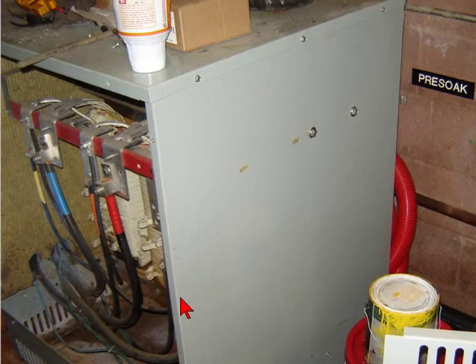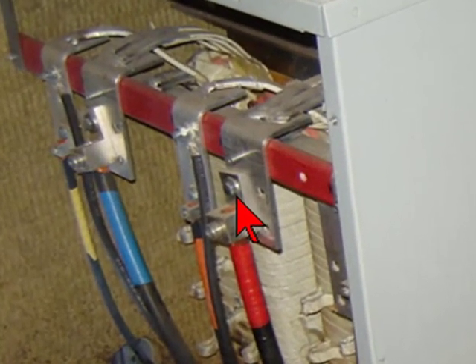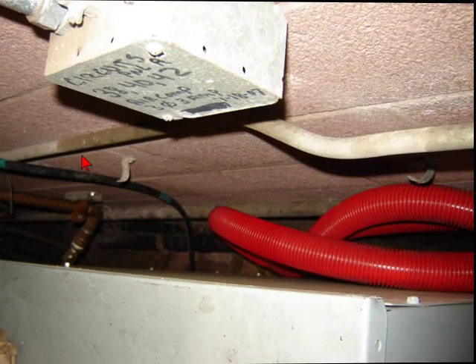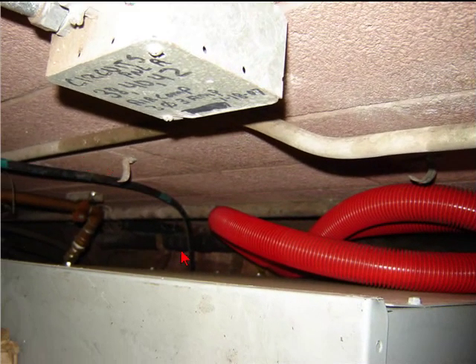There's a job that I went out on recently and we found out that it was a burned-up transformer. A few of the pictures I'm going to show you are close-up pictures of different aspects of the transformer — things that I checked out. I loved checking the tightness of all the fittings, and I had to check the clearance behind the transformer in the wall to verify that there was enough clearance there.